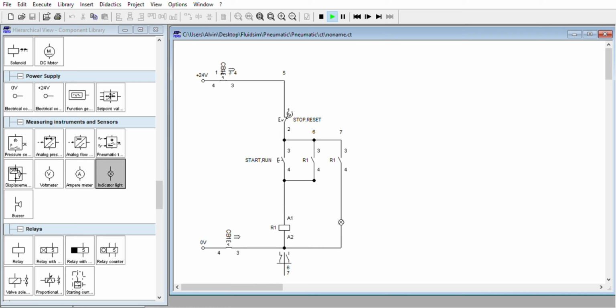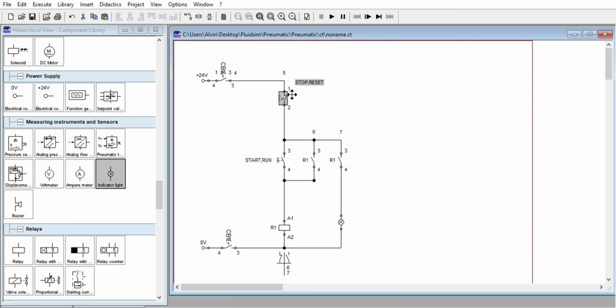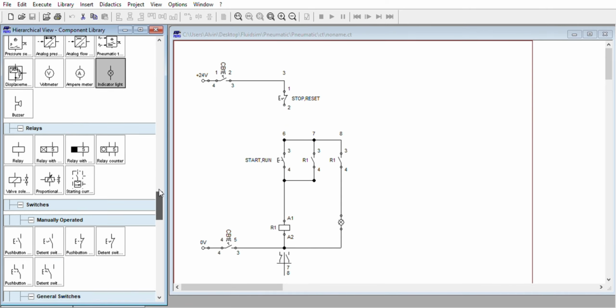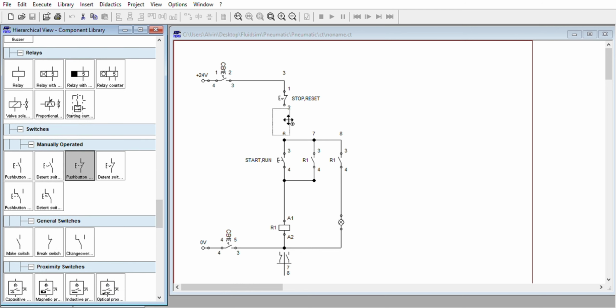Okay, so why this one is detent switch, so that you can make this one as emergency stop also. A regular stop push button is recommended also. So you can series another push button here. If you want the regular push button that is normally close contact at the same time spring return, just remove this one and add the auxiliary push button normally close without the latching operation or not detent. Okay, remember they have different function.